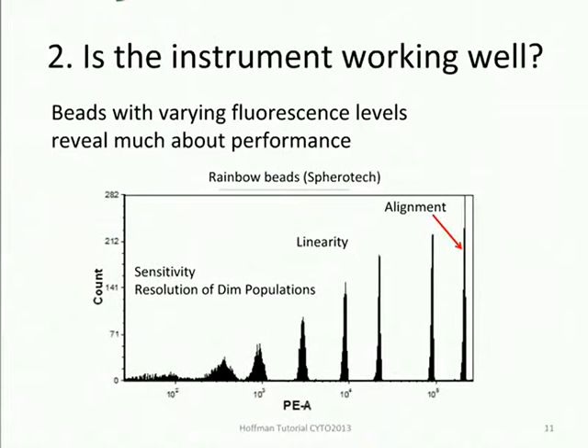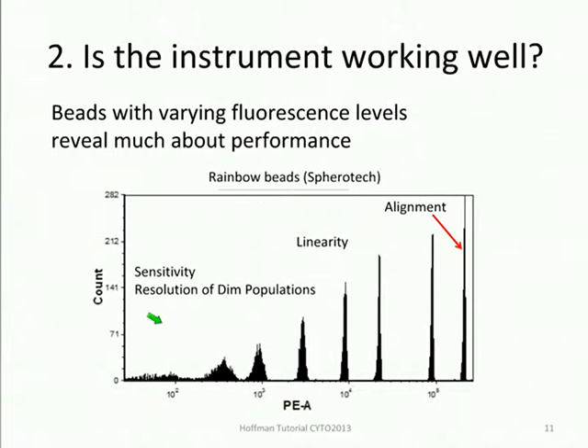A slightly more useful question is: is the instrument working well? This is where multi-intensity beads are useful. The very bright alignment bead with a narrow CV gives the information just described, but beads of different intensity also allow you to establish and quantify system linearity, as well as sensitivity — defined as your ability to resolve very dim populations of particles. Even visually, without quantitative analysis, you can get an idea that the instrument will be able to resolve dim populations.